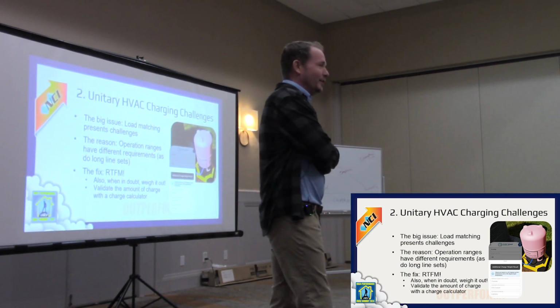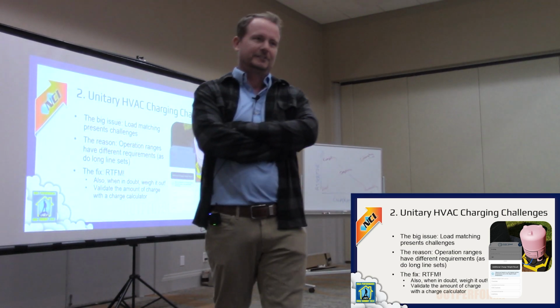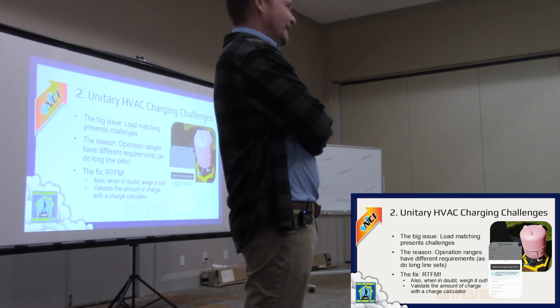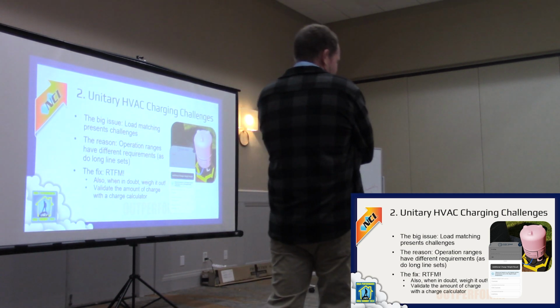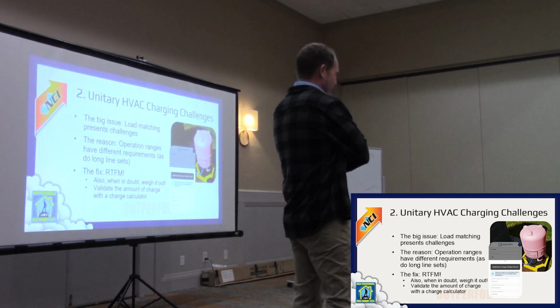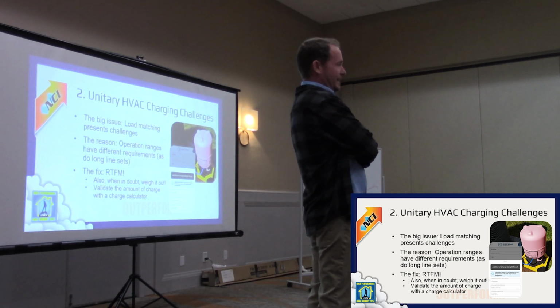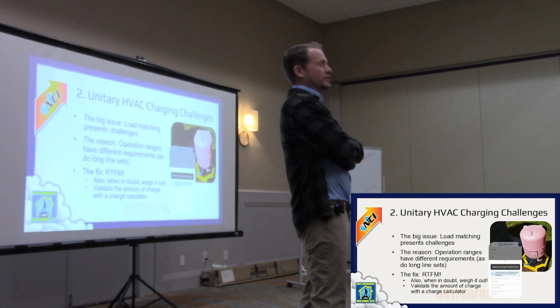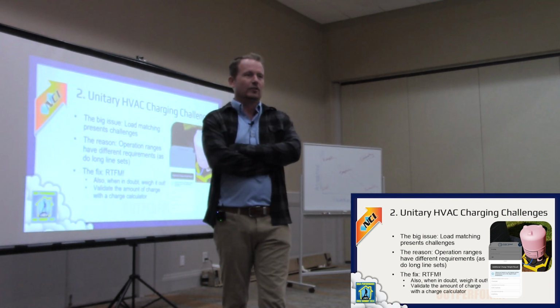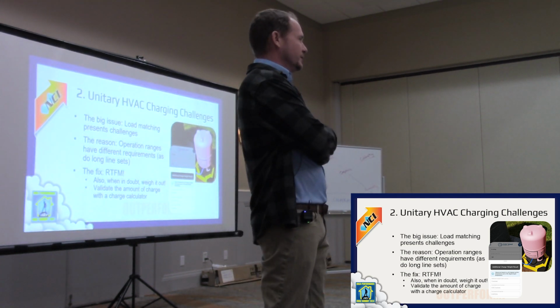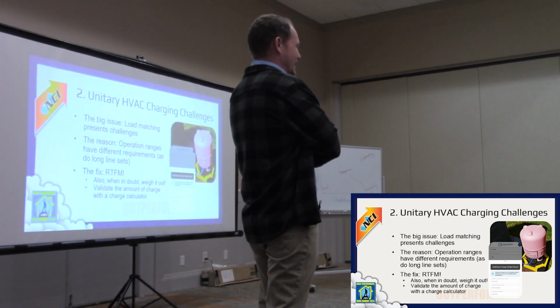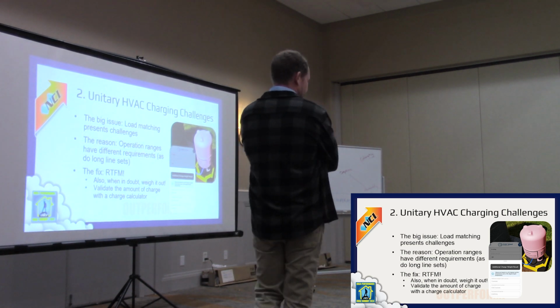Sure enough, we go and pull 20 pounds of extra 410A out of a ductless system. It was a multi-head, but still 20 pounds. Why does anybody ever just add a bunch of refrigerant into a system? What's the one indicator they're looking at? Suction pressure - they're trying to get the suction up, that's what they're always trying to do.